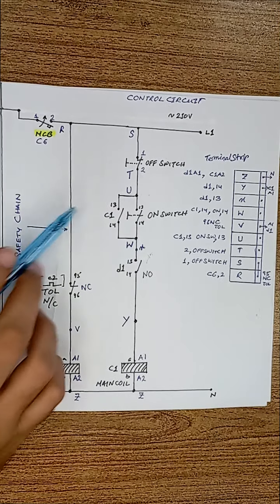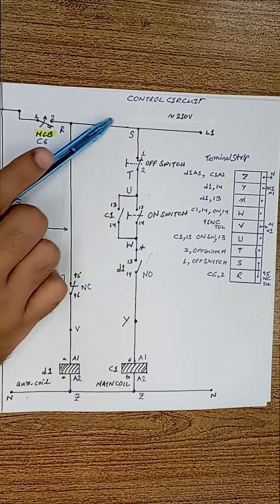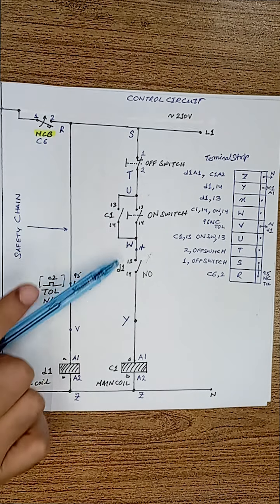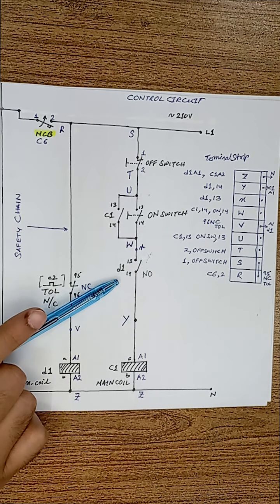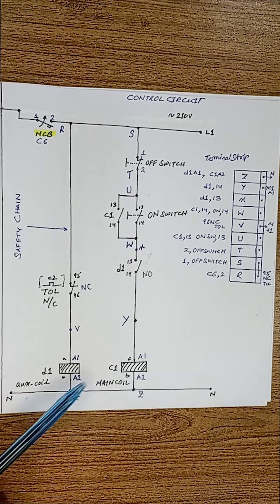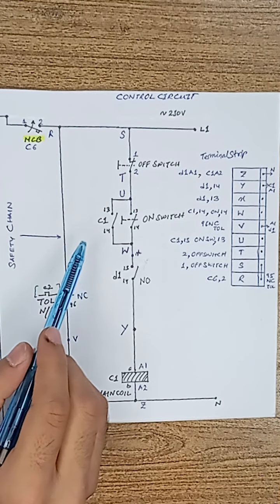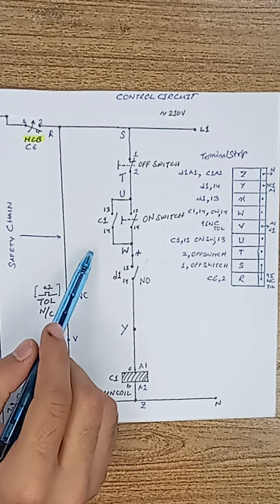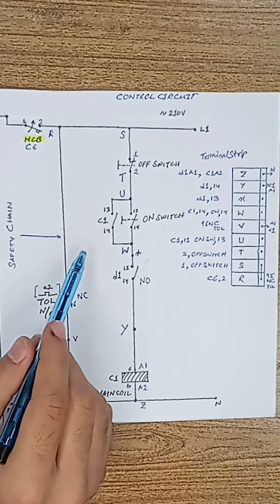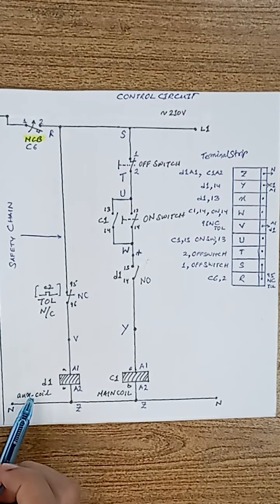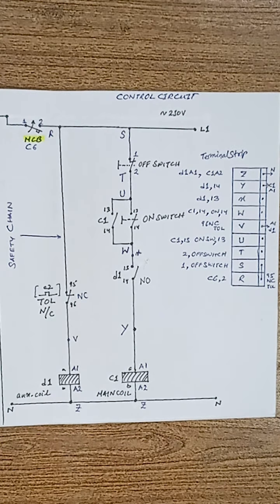When we press the on button, current flows from the single phase source through the normally closed contact of the off button through the normally open contact D1 and energizes the main contactor coil, which leads to the closing of the main contactor contacts and the motor starts to run. The normally open contact C1 is used here to prevent the circuit from powering off. Since it is a normally open contact, it holds the circuit once we let go of the on button by latching onto the source.